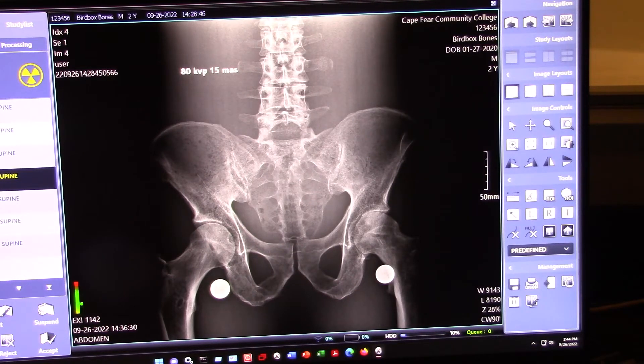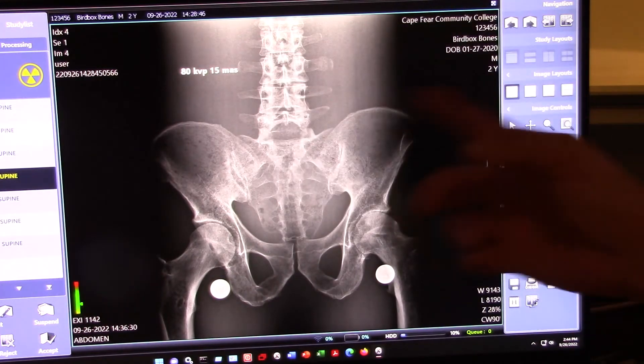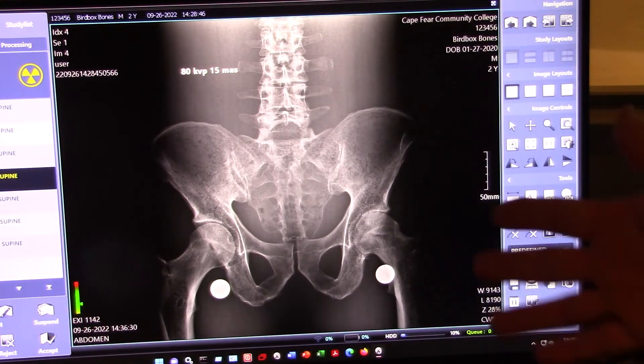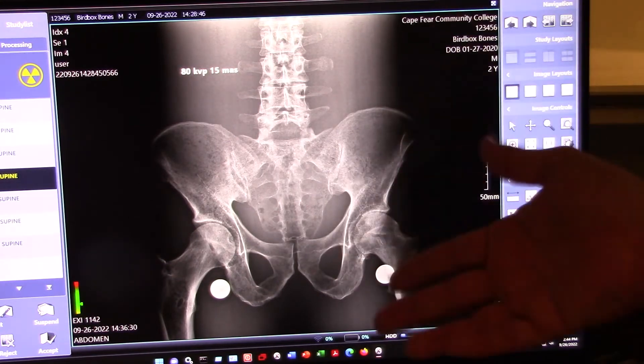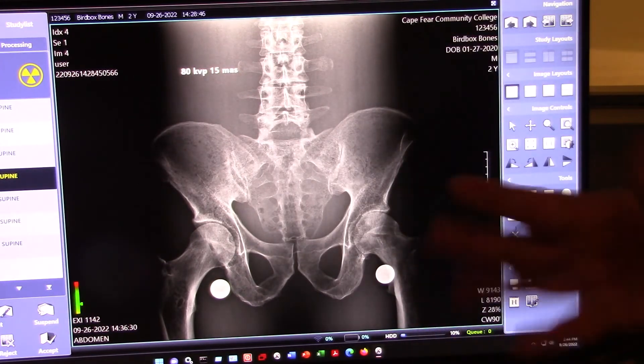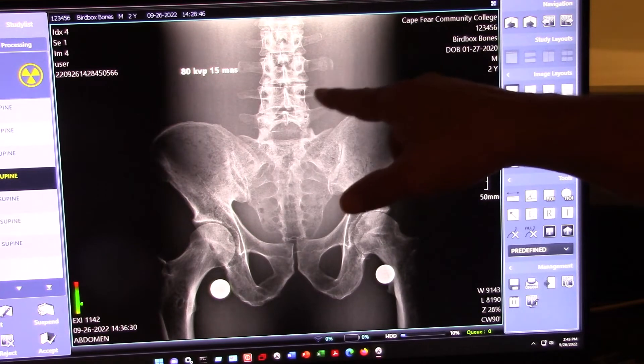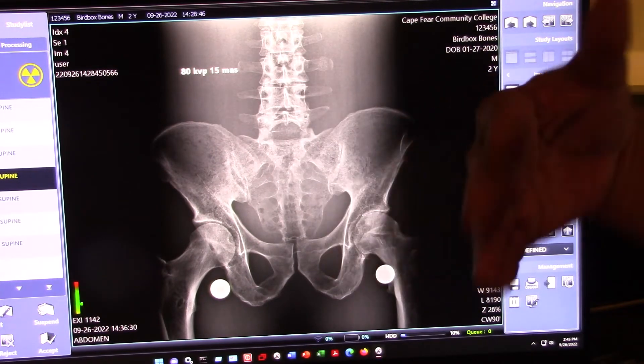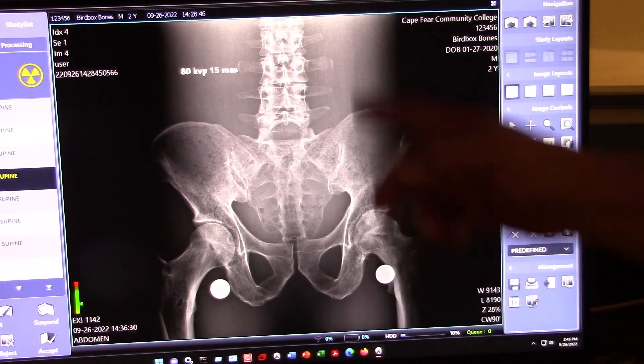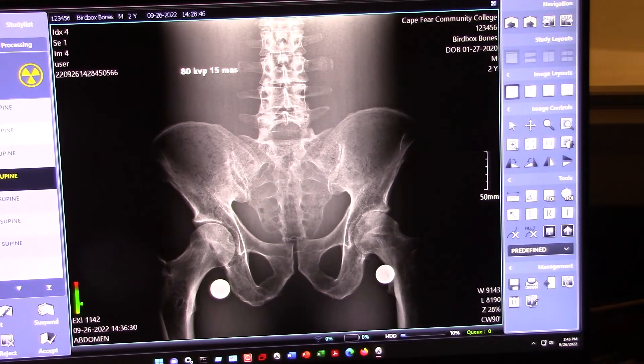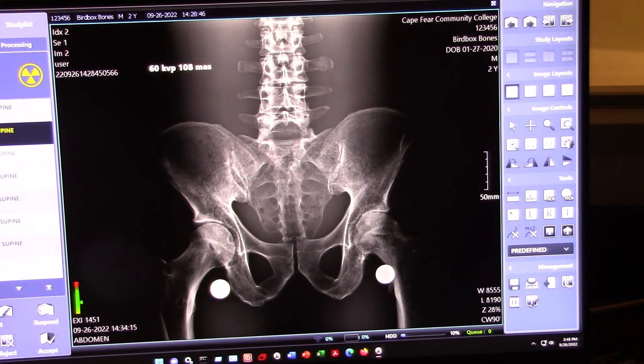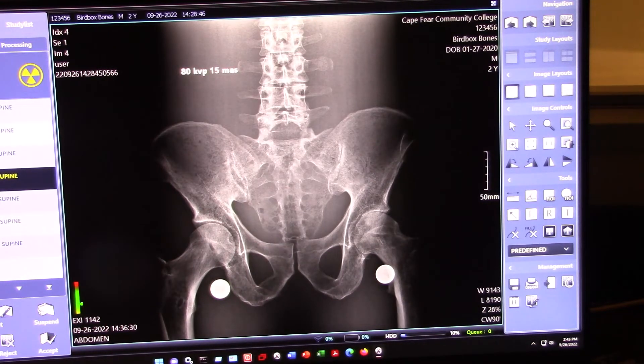here we go to 80 KVP, which is a pretty typical abdomen technique. Now, unfortunately, we don't have any real soft tissue here. If this was a human patient, we'd have intestines and things in here so that we would be able to see if those were demonstrated well. As it is, we're restricted to just bones. But still, you can see where the bones start and stop. So, still a relatively high contrast image, but not as high as it was to start with.